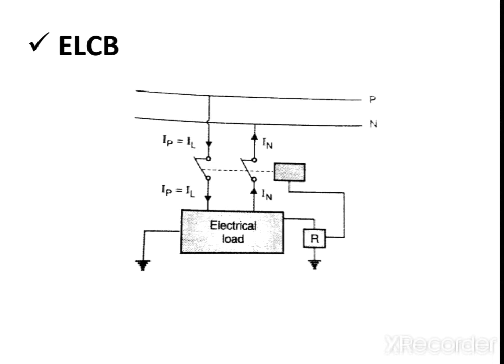This is the basic diagram of ELCB. The electrical load is connected through the relay, and one terminal of the relay is connected to the electrical load and another is connected to the ground. The supply is from phase and neutral. In normal operating condition, as the arrows show here, the phase current is provided and the neutral current is going out.